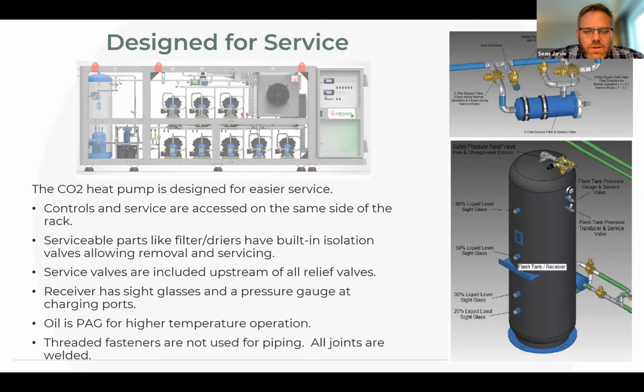Another interesting thing with CO2 is the pressure is higher by about a factor of 3 than 410A. So we're talking maybe 1600 PSI to 1700 PSI on the highest side of the transcritical system. No tech really wants to put on gauges at that because their gauges might only be rated to 800 PSI. So with that, we incorporate gauges and pressure transducers going right to the controller. So the only time we really need to do anything with them is on initial calibration on startup. After that point, you have at least 2 points of reference to make sure your high side is always under control. Your low side has all that too.